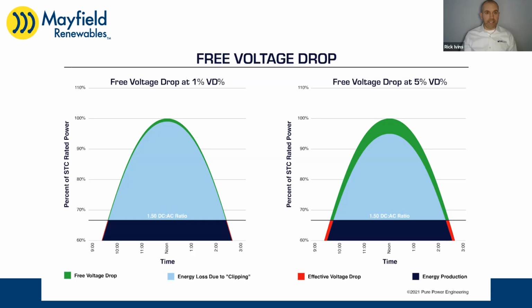If you realize that, you might say, why drive the voltage drop so low? Let me accept some and optimize more for performance rather than just voltage drop. Then you can really start to drive down the cost of the installed system, reducing CapEx, while having a negligible effect on energy output. There's still some effect, but the CapEx savings are usually much more than the lifetime gain you'd get from driving down voltage drop.